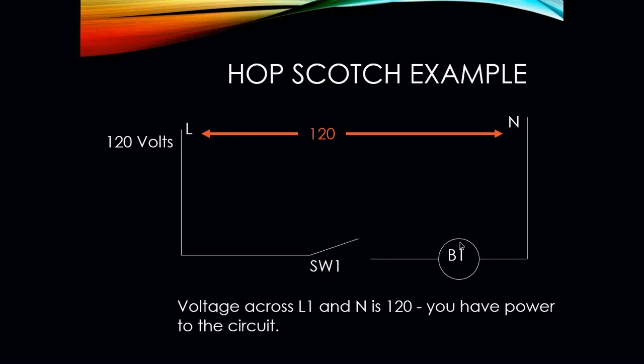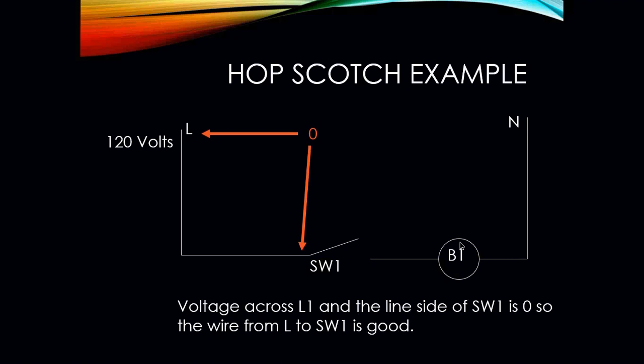So here we go. Here's an example. We have a 120 volt circuit here with a switch and one load. Okay, across L1 and neutral, we are reading 120 volts. That is indicating that we do have power on this circuit. That's a good thing. If we have 0 volts there, that's telling us that we do not have power at this circuit, and there's a problem before this circuit. So that could either be a breaker, or maybe the emergency switch at the top of the stairs, something like that. So always make sure you go across the entire circuit first to make sure that you have voltage. So in this case, 120 volts.